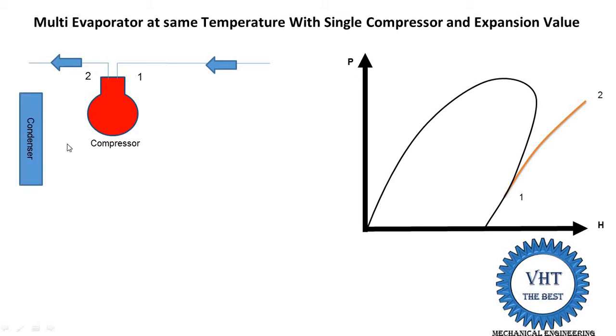This high pressure vapor refrigerant is supplied into the condenser. The condenser is a heat exchanger in which heat is rejected using a fan. Process 2 to 3 is isobaric heat rejection — isobaric means constant pressure. The temperature also remains constant but the phase changes: at the inlet of the condenser it is vapor phase, and at the outlet it is liquid phase.